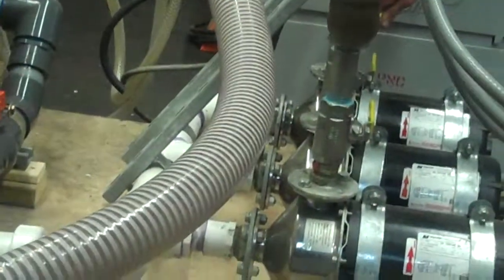What we're going to do right now is Dana is throttling back on one of the pumps. It'll take a second, but if you only have one yellow light, that means you don't have enough flow, or the flow switch is not being made. So we should see that in a second. You can see right there, we only have one yellow light on, so the switch is not being made. Okay, let's get it.